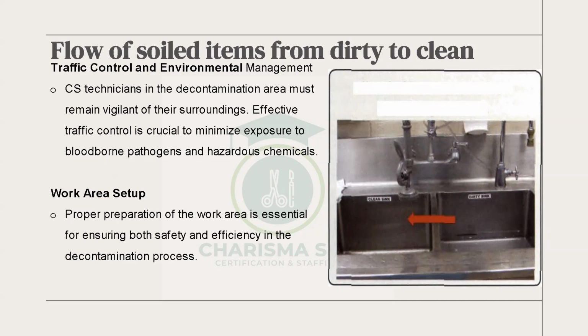This is the flow of soiled items from dirty to clean, which I mentioned already. All soiled items should flow from dirty to clean, and that is the one-way traffic I'm telling you about. It must be from dirty to clean, that's the traffic, it must not be mixed up anywhere. So if the sink, you see in the image, you see 2 sinks.